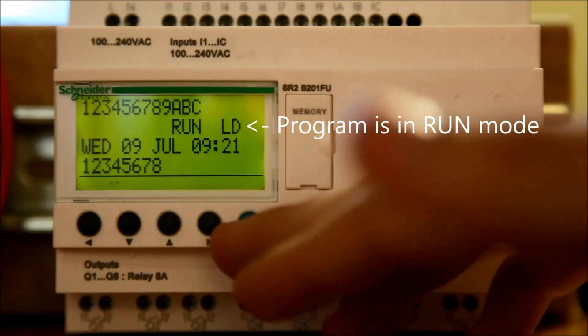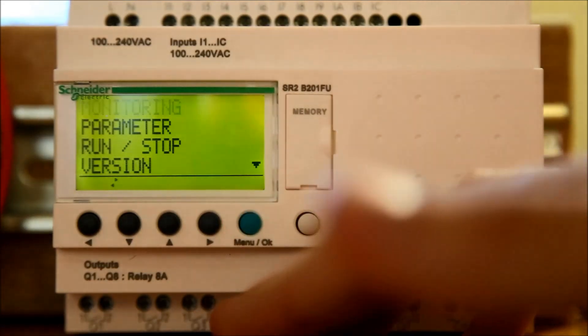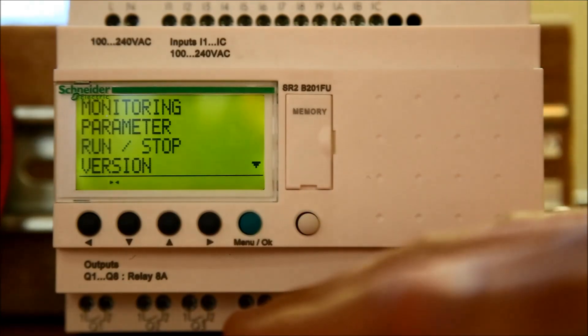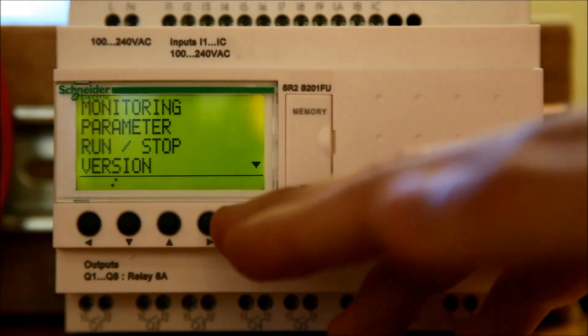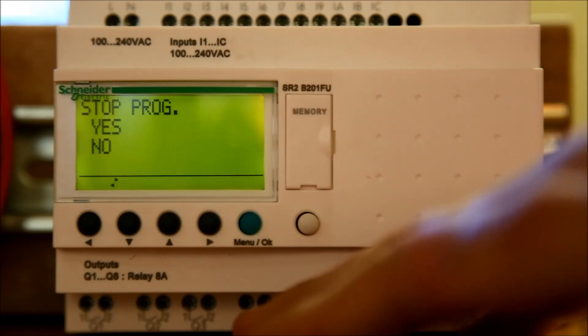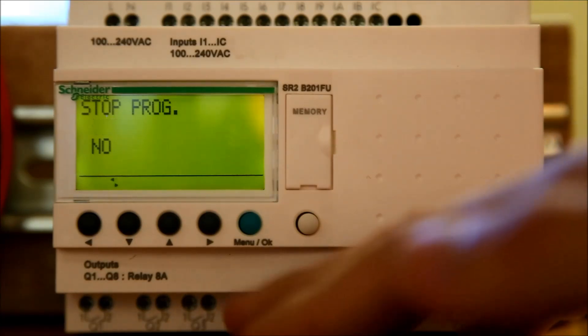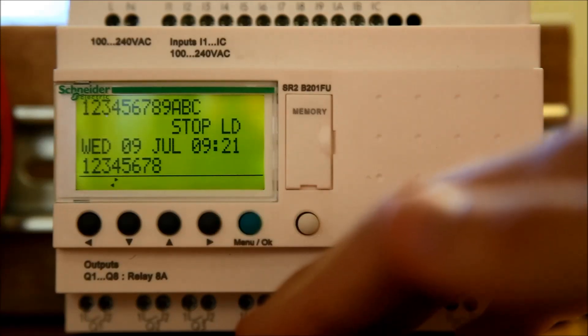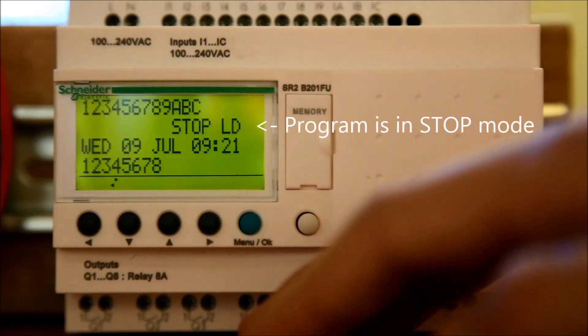You'll want to ensure the program on the Zelio is stopped. If it is running, press the Menu OK button and use the up and down arrows to scroll to the Run Stop option. Press the Menu OK button. A confirmation screen will now appear. Make sure Yes is selected and press the Menu OK button. The program should now be stopped as indicated on the screen.